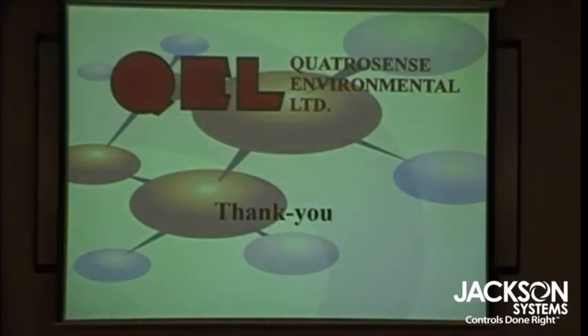Some of our competitors, you know, if you buy a sensor, you may as well buy a new transmitter. In our case, it's very, very economical. And you can plug the sensor in, or you can buy a sensor with the board pre-calibrated and plug it in also. And I would recommend that for some of the weird gases. So if you're doing ammonia or something, it's cheaper to buy a sensor than to buy a whole cylinder of gas. Ammonia gas is extremely expensive. And the other thing is, it's a reactive gas. They only guarantee it for a year in the cylinder. So after a year, it's no good.